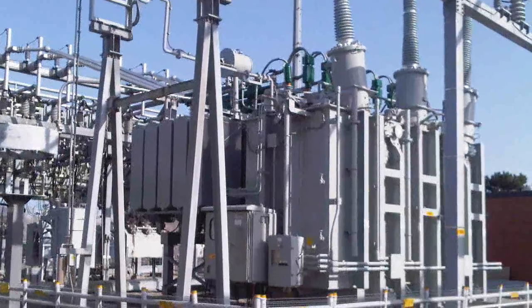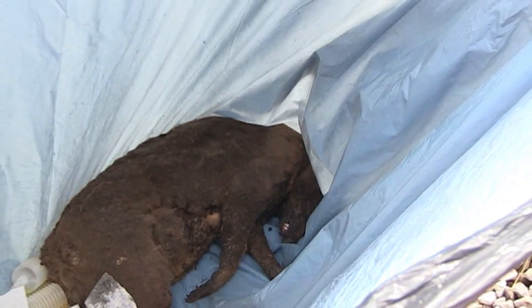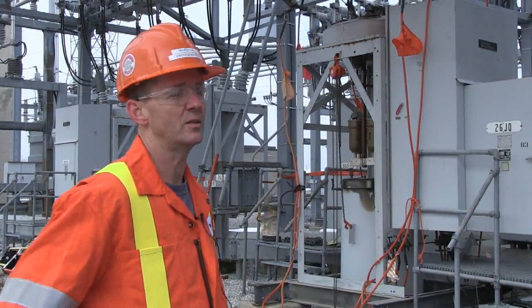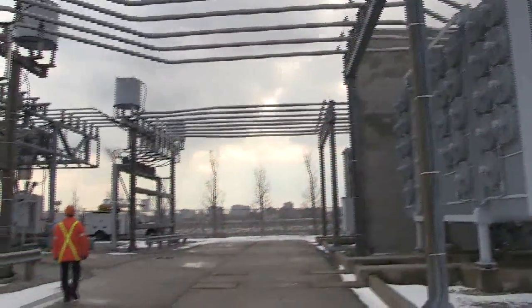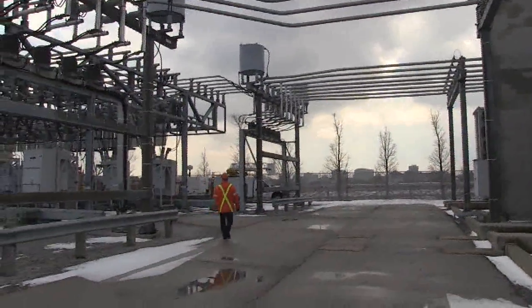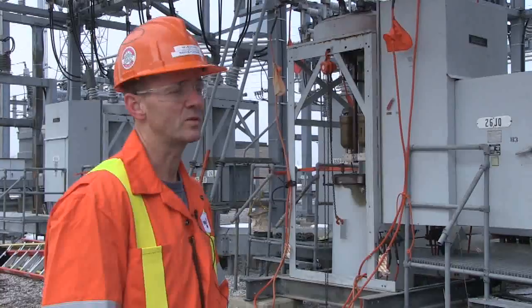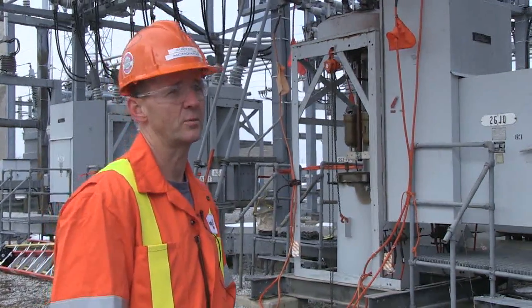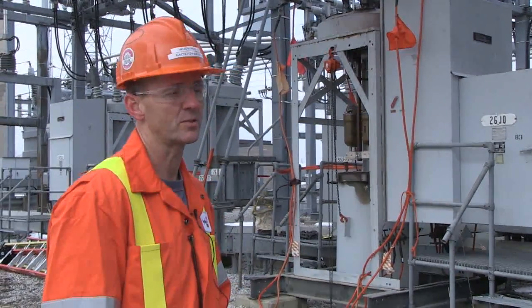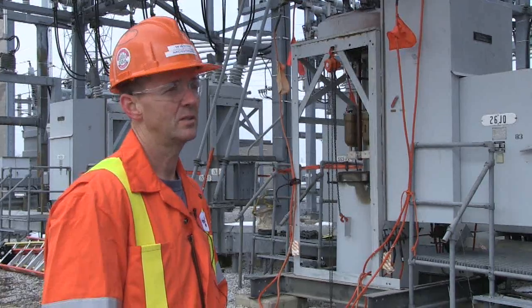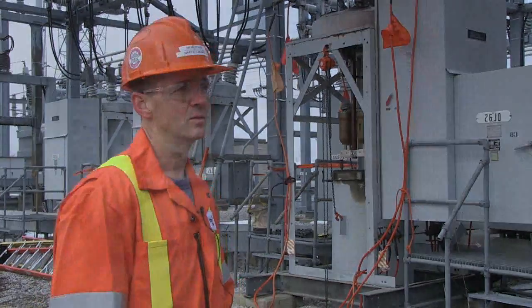And on February the 7th, we had a live animal contact. In this case, the raccoon got up on top. He had electrical contact, which caused a fireball. It was like an energized cloud, and it took out both the J and the Q buses at Malvern. 65 megawatts of load was interrupted. Once the fault cleared through protections, through P&C, the operators re-energized the buses and got the load back.